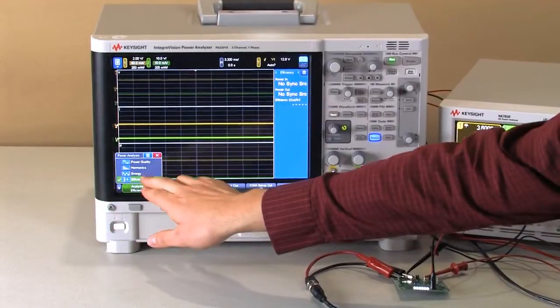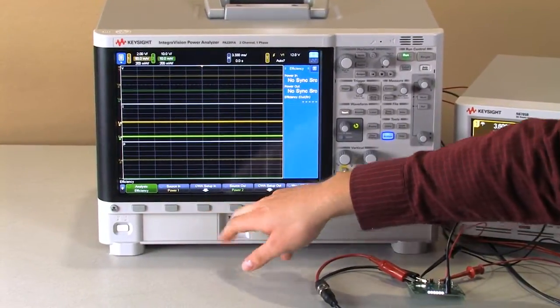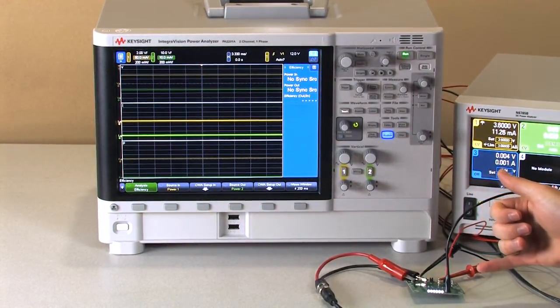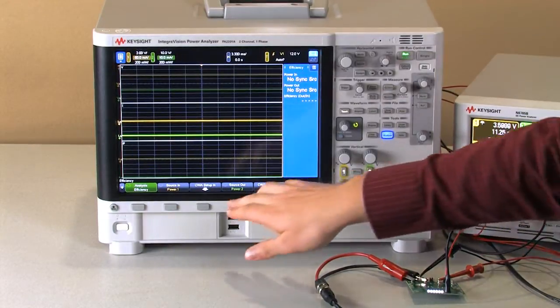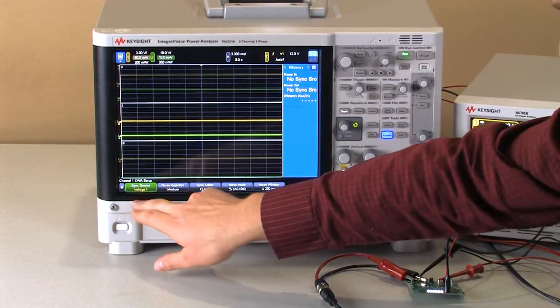So I go to Analyze to run efficiency mode, and since we're measuring DC power on both channel 1 and channel 2, we need to set the trigger to be line trigger for both channel 1 and channel 2.